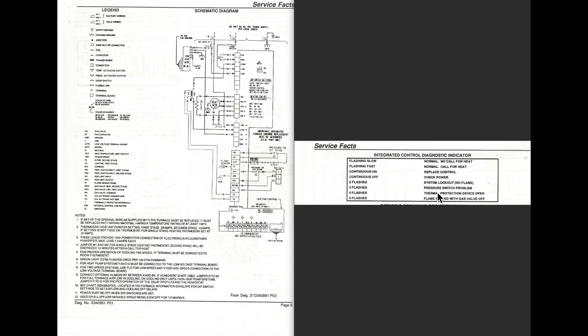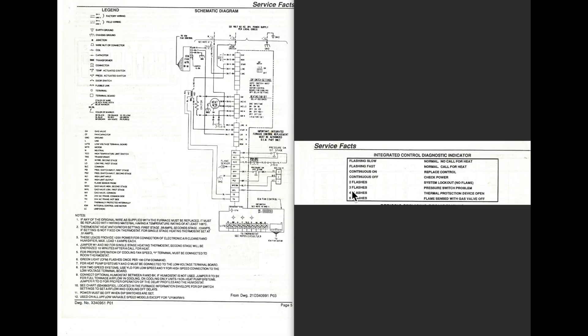Three flashes is a pressure switch problem. It's not telling you the pressure switch has failed. It's telling you it's a pressure switch problem. The inducer didn't come up to speed. Maybe it didn't come on at all. Maybe you got a blockage in the vent. All those things could cause a pressure switch problem.